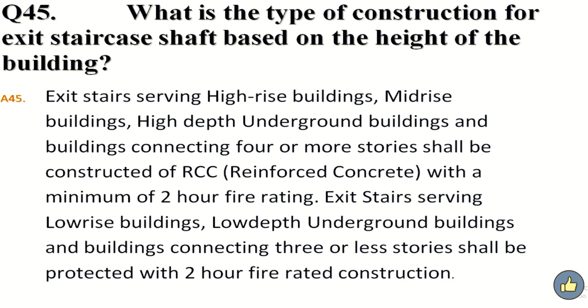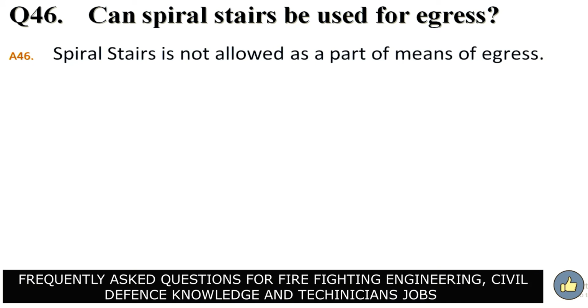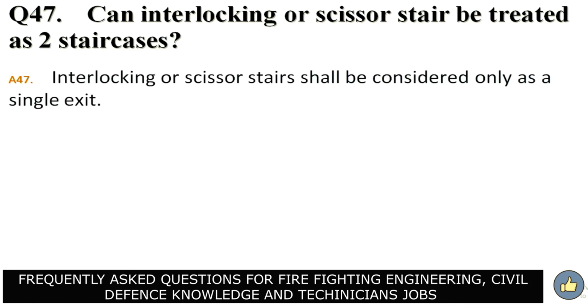What is the type of construction for exit staircase shaft based on the height of the building? Answer. Exit stairs serving high-rise buildings, mid-rise buildings, high-depth underground buildings, and buildings connecting 4 or more stories shall be constructed of RCC reinforced concrete with a minimum of 2-hour fire rating. Exit stairs serving low-rise buildings, low-depth underground buildings, and buildings connecting 3 or less stories shall be protected with 2-hour fire-rated construction. Can spiral stairs be used for egress? Answer. Spiral stairs are not allowed as a part of means of egress. Can interlocking or scissor stair be treated as two staircases? Answer. Interlocking or scissor stair shall be considered only as a single exit.